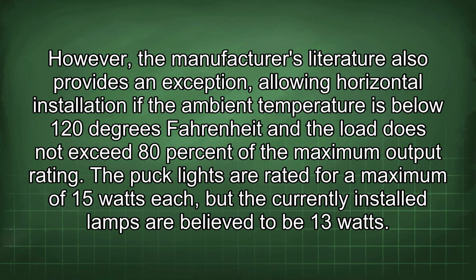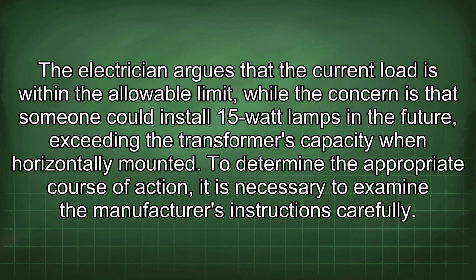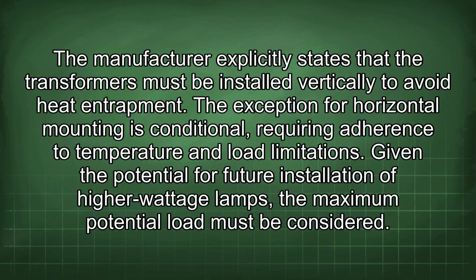The puck lights are rated for a maximum of 15 watts each, but the currently installed lamps are believed to be 13 watts. The electrician argues that the current load is within the allowable limit, while the concern is that someone could install 15-watt lamps in the future, exceeding the transformer's capacity when horizontally mounted. To determine the appropriate course of action, it is necessary to examine the manufacturer's instructions carefully. The manufacturer explicitly states that the transformers must be installed vertically to avoid heat entrapment. The exception for horizontal mounting is conditional, requiring adherence to temperature and load limitations.